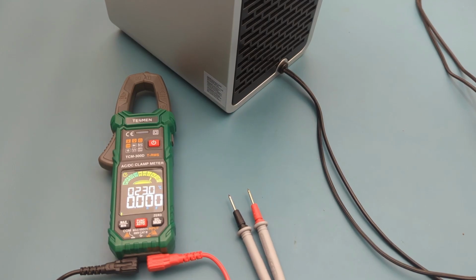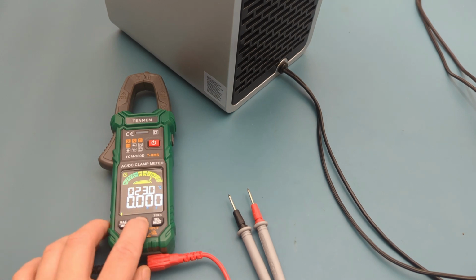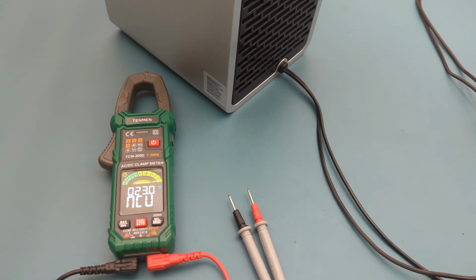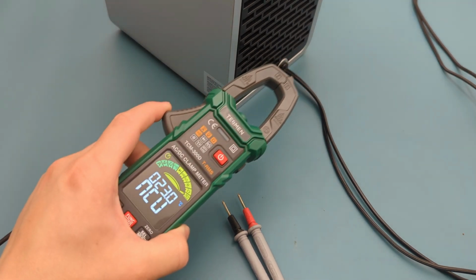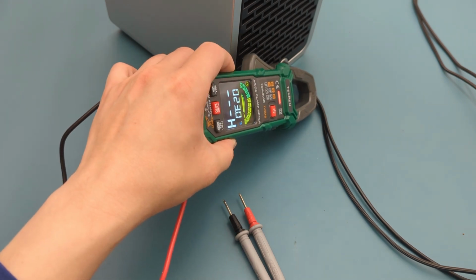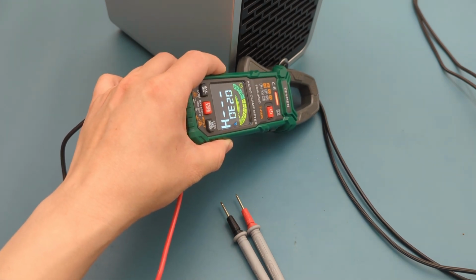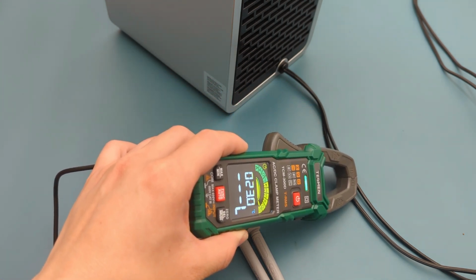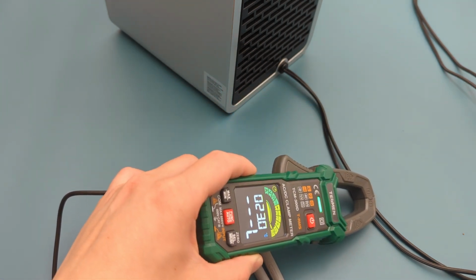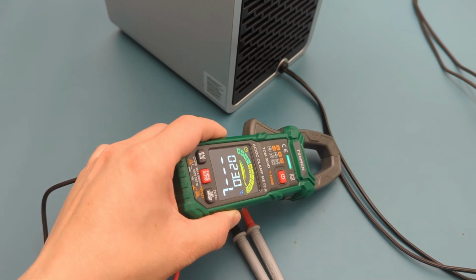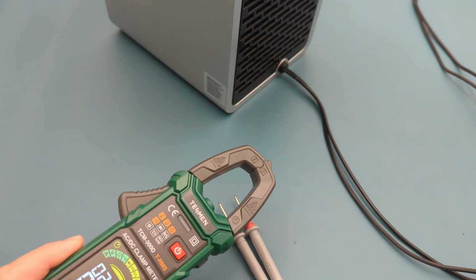The next test is to do the non-contact AC voltage detection. Press the function button to change to the NCV mode. The tip of the meter is the NCV probe. When a strong electric field signal is detected, the letter H is shown on the display. The alarm indicator shows a red light. When a weak electric field signal is detected, the display shows the letter L. The alarm indicator also shows a green light.